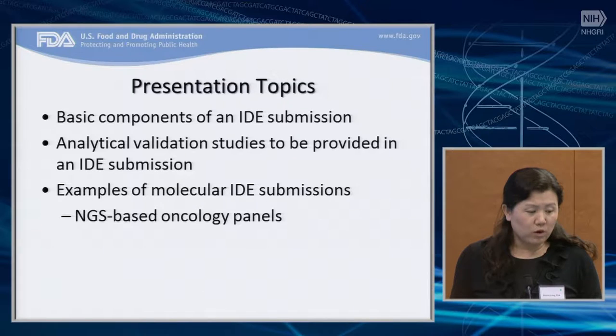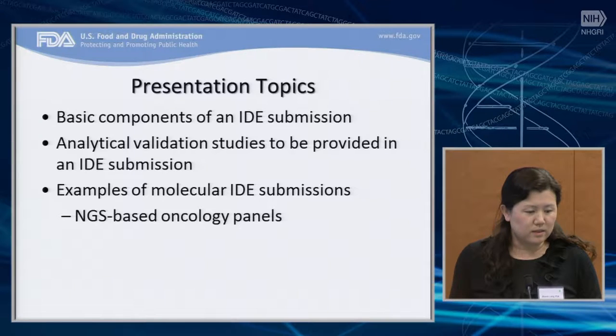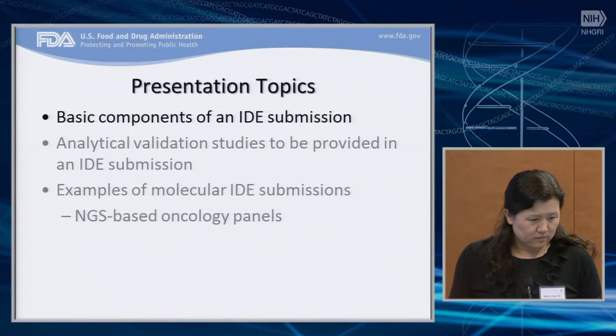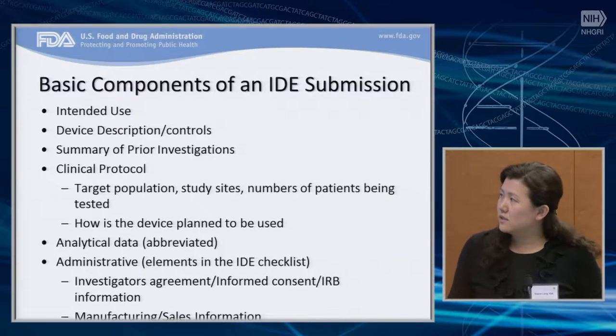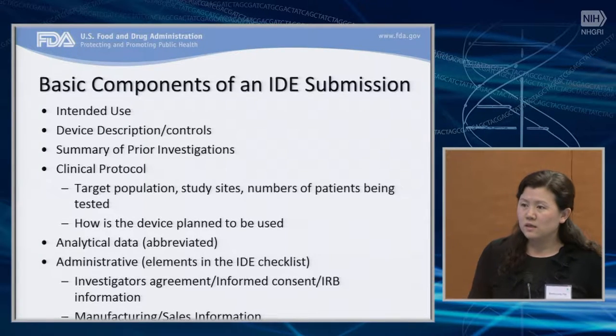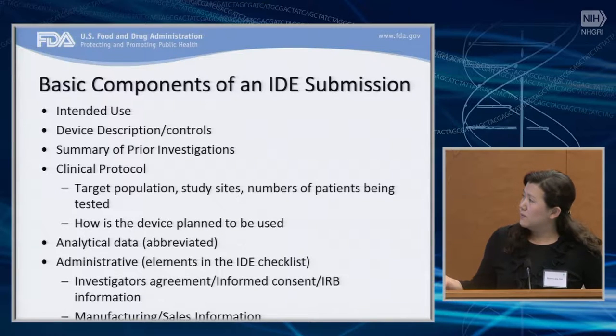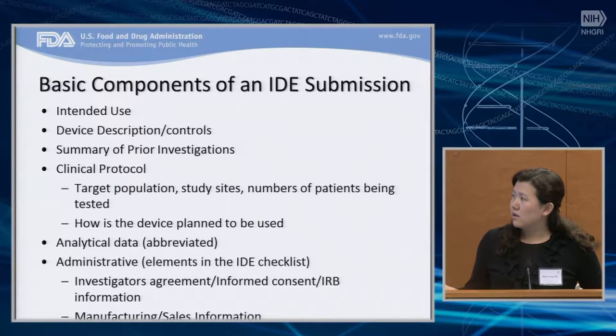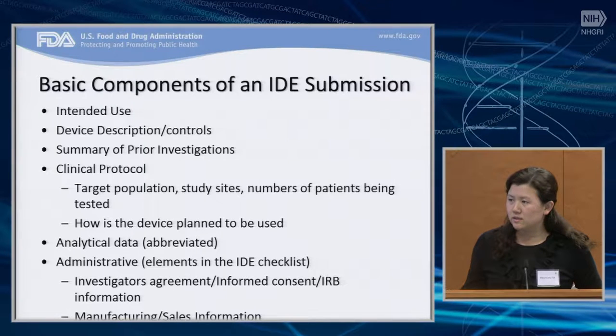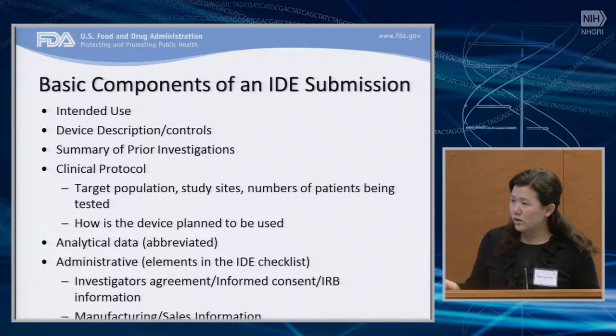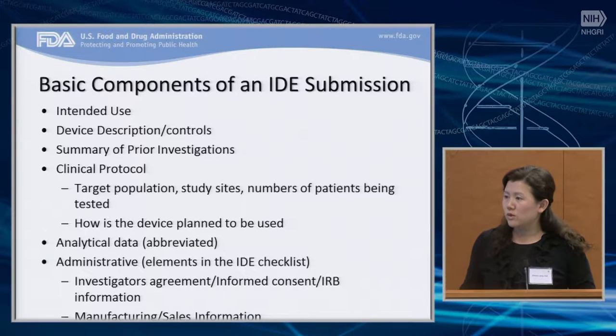I will use one example to demonstrate the analytical studies submitted to the IDE submission. This slide lists basic components of IDE submission. Basically, we like to see what your device is intended to be used for, and then how your device looks, and what components you have in your device. Jonathan asked questions earlier about how you define the device — it's your choice based on your purpose in the clinical trial, so you can define what components you have.